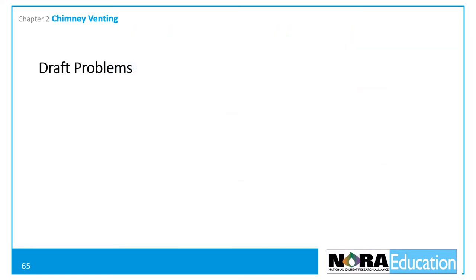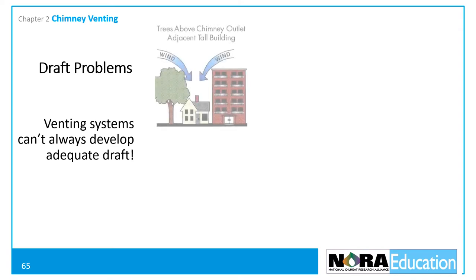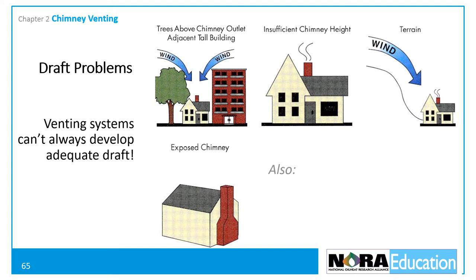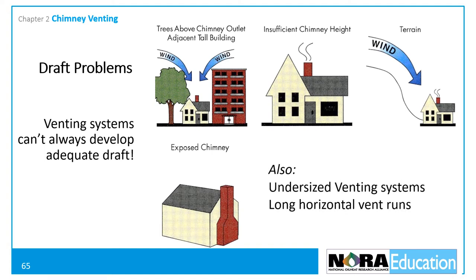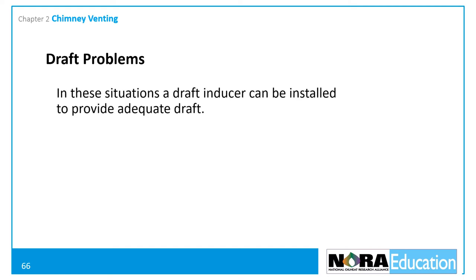Sometimes the venting system cannot develop sufficient draft to safely vent the combustion gases from the building. Downdrafts due to outside influences, short chimneys, terrain, outside exposed chimneys, undersized venting systems, long horizontal vent runs, and negative building pressure can cause draft problems. When the venting system cannot develop sufficient draft, a draft inducer — also known as a draft fan — can be installed to provide the necessary draft.